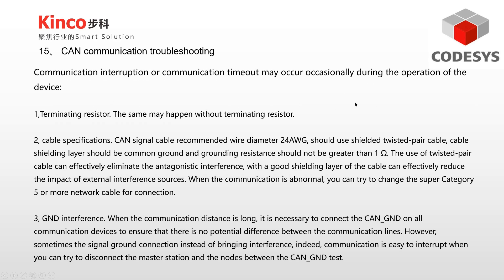Third, check the cable. It is recommended to use 24 AWG shielded twisted pair cable. Cable shielding layers should share a common ground and grounding resistance should not be greater than 1 ohm. When communication is abnormal, you can try changing to Category 5 or higher network cable for connection. Regarding GND interference — when the communication distance is long, it is necessary to connect the CAN GND on all communication devices to ensure there is no potential difference between the communication lines.